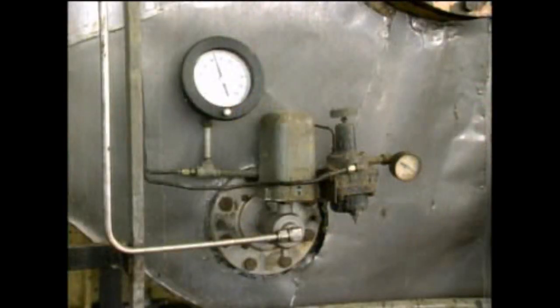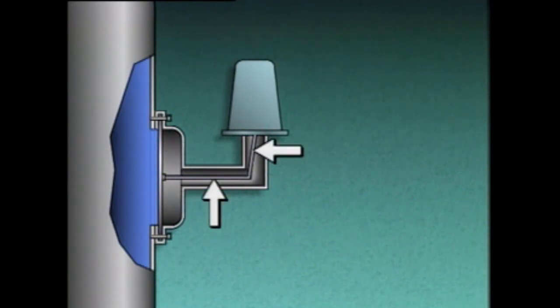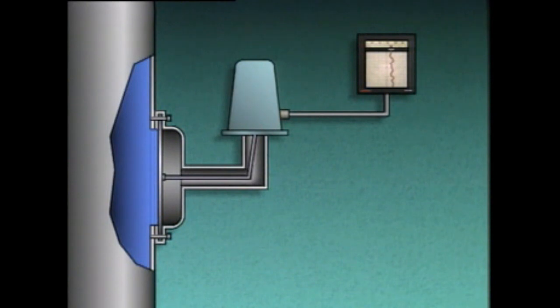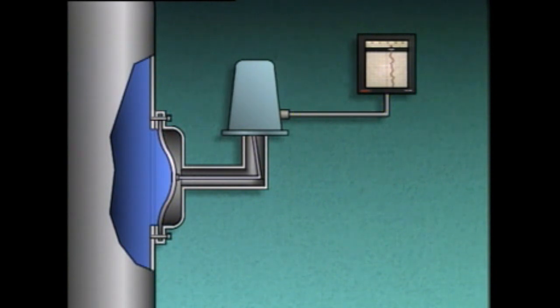Sometimes pressure indications need to be sent to other devices in remote locations, such as a recorder located in a control room. One device used for this purpose is a pressure transmitter. Here's a simplified illustration of a pressure transmitter installed on the side of a tank containing a liquid. A diaphragm pressure element is mounted onto the tank and connected through a mechanical linkage to the transmitter, which in turn is connected to a recorder. During operation, the liquid in the tank exerts pressure on the diaphragm causing it to bulge. The transmitter then transmits a proportional signal representing the pressure in the tank to the recorder, which provides the pressure indication.